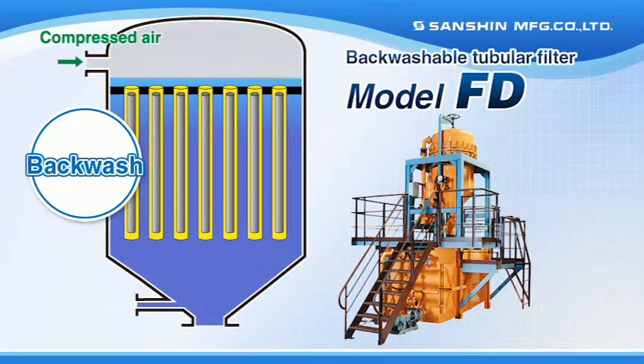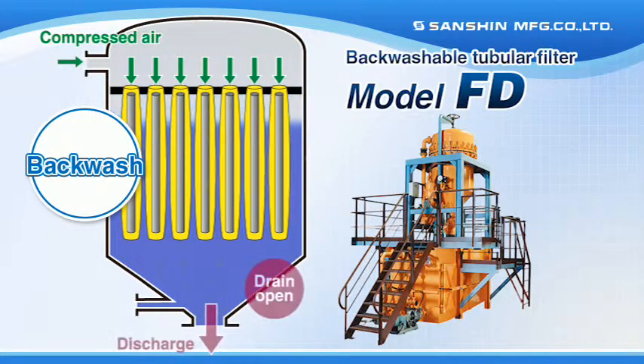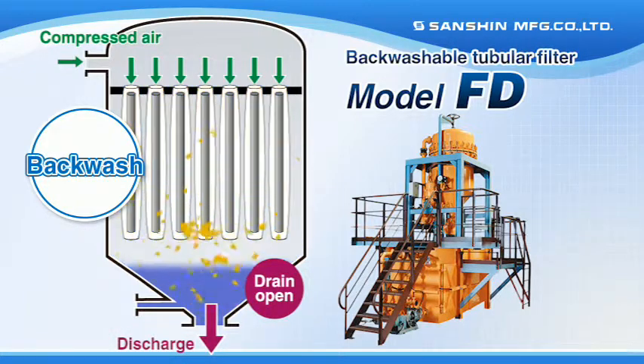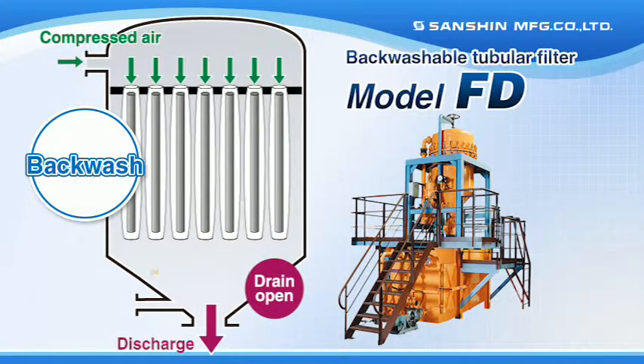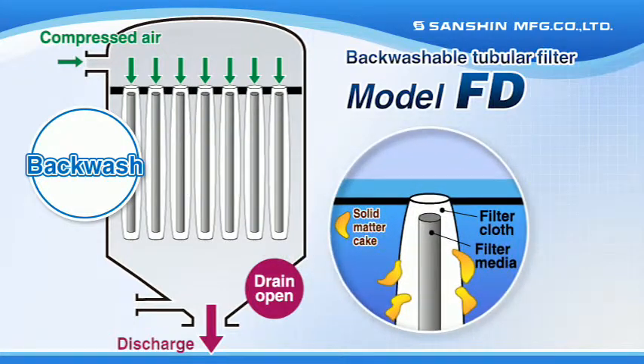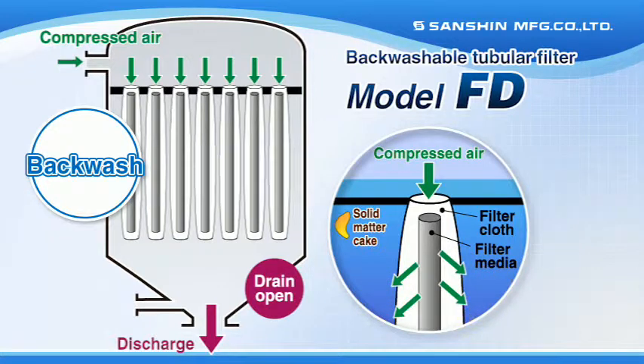By applying constant pressure with air from the filtrate side and opening a drain valve at the bottom of the filter once filtration is complete, suspended solids captured on the filter cloth surface are rinsed out with pressurized filtrate from the reverse side of the filter media and then expelled outside the system. Not only can filter media performance be restored extremely quickly, but filter media can be used repeatedly, leading to reduced waste.